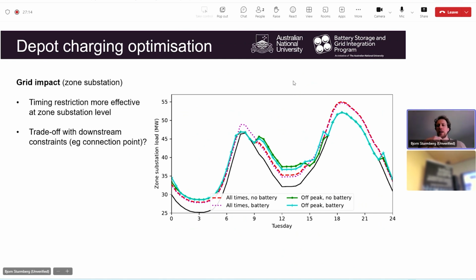And what's interesting about why I've presented this is that those four scenarios, collectively, demonstrate that there can be a tension between reducing the grid impact of a bus depot or any other charging. There's a tension between impacts at the point of connection of the bus depot, where the absolute peak power that you place on the network is the criteria that's of relevance, and the impacts on the zone substation, so at a higher aggregate level in the network, where in this case, the higher peak load in the middle of the day isn't an issue, whereas any load at all that's added during the evening is an issue.